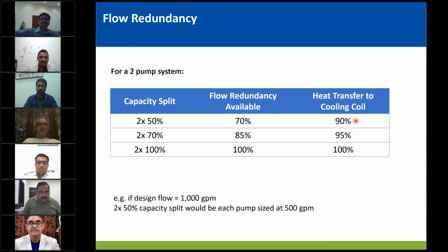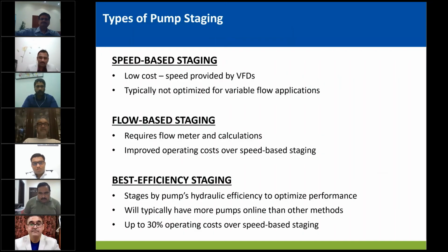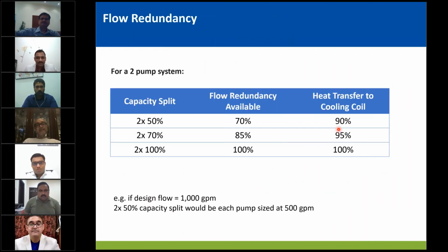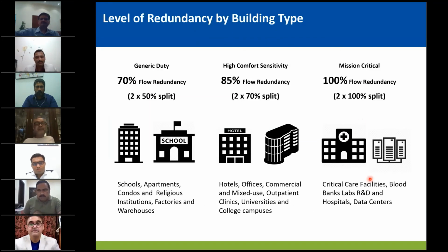And if you take the next level, which is a 2 into 70% flow split for the pumps, you still have 85% flow redundancy, and that gives 95% cooling transfer capacity. And finally, the 100% for mission critical.